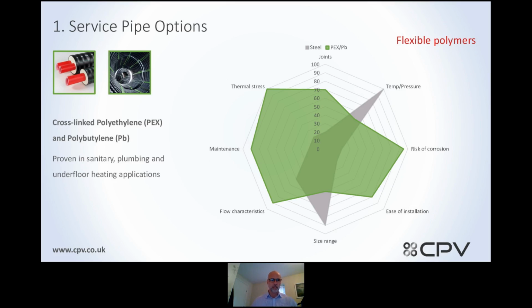On the next slide, I'm going to discuss some of the flexible polymers. First off, the greyed out area on the spider graph relates to steel pipework systems. Steel does have an effect on temperatures and pressures. It'll do the higher pressures and temperatures, and the size range is there. But one of the key factors is the risk of corrosion if the systems are not installed correctly. You need to consider thermal stresses on the systems, maintenance, and the flow characteristics.